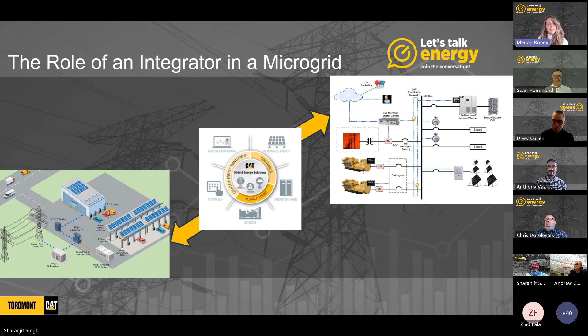Sure. Well, the switchgear often gets overlooked. And as Anthony mentioned, integration does drive performance. So today, one of the things we want to talk about when integrating a system is the role the switchgear plays in a microgrid and how important it becomes when multiple energy sources are connected. Think of it like a traffic cop or musical conductor. Shown here, it physically connects and disconnects sources and loads, as it's the common point of AC coupling for energy systems. It's also where energy performance is typically captured for key automation decisions.